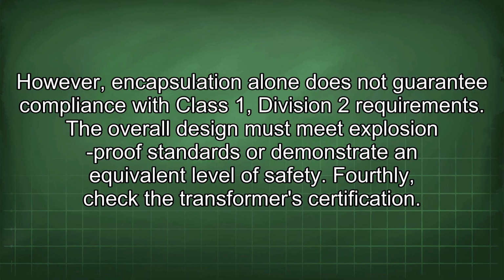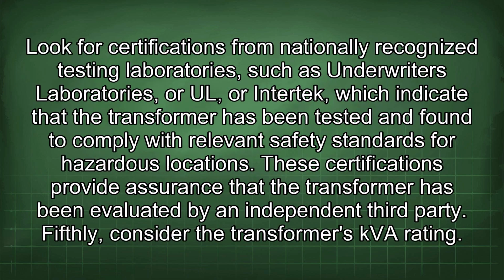Fourthly, check the transformer certification. Look for certifications from nationally recognized testing laboratories such as Underwriters Laboratories, or UL, or Intertek, which indicate that the transformer has been tested and found to comply with relevant safety standards for hazardous locations. These certifications provide assurance that the transformer has been evaluated by an independent third party.